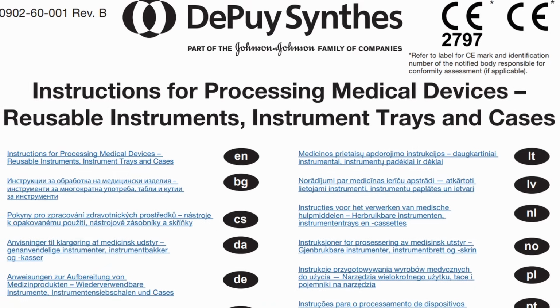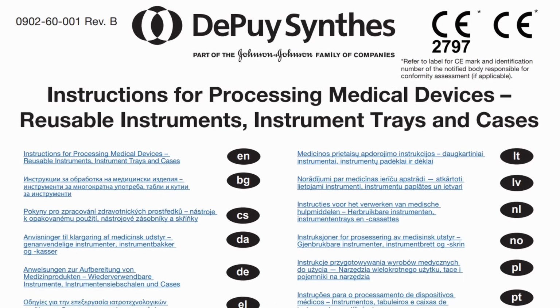Here in Prep and Pack, there's a lot of steps that are taken to ensure instruments meet strict quality measures in order to move forward in the process. All instruments have different requirements, and you must refer to what is known as the Instructions for Use, or IFU for short. These are provided by the manufacturer for each and every instrument. An IFU is a manufacturer document which breaks down the proper and validated steps to handle, clean, disinfect, sterilize, and even store instrumentation. It also dictates the temperatures and times of steam sterilization cycle parameters, as well as low temperature cycle parameters, and any other type of sterilization or disinfection process.